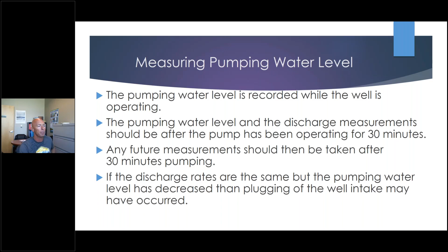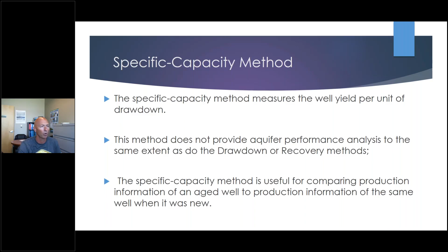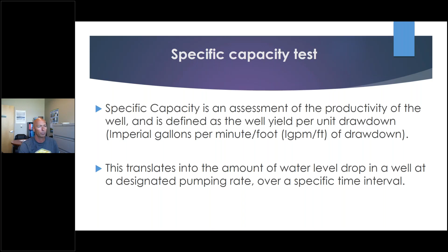Specific capacity method. The specific capacity method measures the well yield per unit of drawdown. This method does not provide aquifer performance analysis to the same extent as do the drawdown or recovery method. The specific capacity method is useful for comparing production information of an aged well to production information of the same well when it was new. Again, huge information to take all those numbers down and compare them. So again, as I said before, specific capacity is an assessment of the productivity of the well and is defined as a well yield per unit drawdown, imperial gallons per minute per foot of drawdown. This translates into the amount of water level drop in a well at a designated pumping rate over a specific time interval. So time off, time on, and then pumping rates.